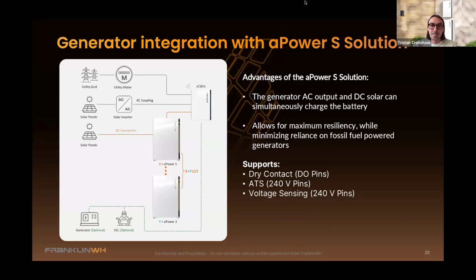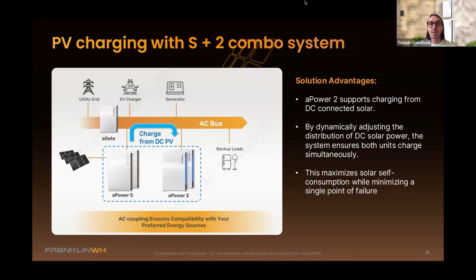Another question about these combination systems: how does the PV resource charge both batteries simultaneously? Do I need AC coupled solar with the aPower 2 if I have an aPower S? What happens is we're just balancing the charging from the DC connected solar across multiple batteries, so as with any AC coupled Franklin system, the aPower S and aPower 2 would essentially be balanced in terms of charge and discharge capability, so the SOC should remain almost identical. There's slightly more efficiency charging the aPower S from the DC PV connection, but it's spread across any battery evenly.